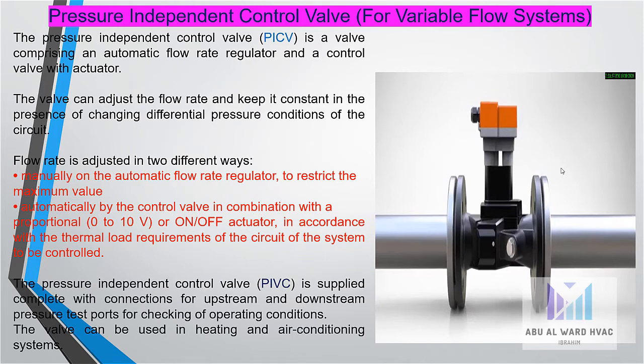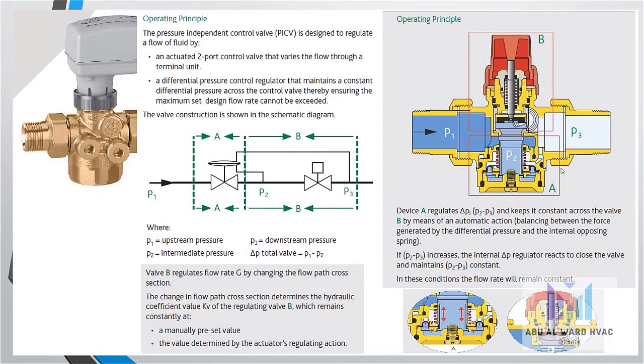The pressure independent control valve PICV is supplied complete with connections for upstream and downstream pressure test ports for checking of operating conditions. The valve can be used in heating and air conditioning systems. This is the operating principle of the PICV.